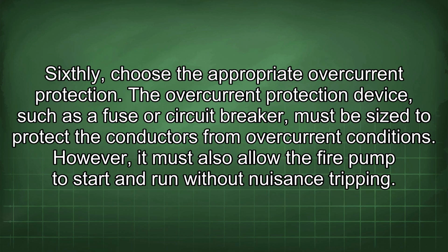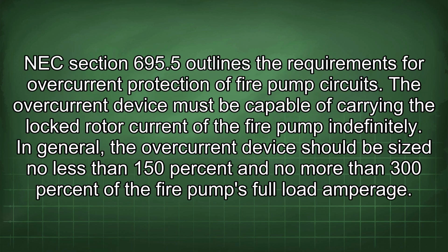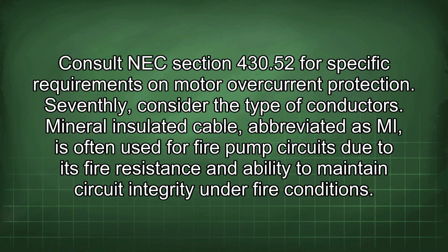Sixthly, choose the appropriate overcurrent protection. The overcurrent protection device, such as a fuse or circuit breaker, must be sized to protect the conductors from overcurrent conditions. However, it must also allow the fire pump to start and run without nuisance tripping. NEC Section 695.5 outlines the requirements for overcurrent protection of fire pump circuits. The overcurrent device must be capable of carrying the locked rotor current of the fire pump indefinitely. In general, the overcurrent device should be sized no less than 150% and no more than 300% of the fire pump's full load amperage. Consult NEC Section 430.52 for specific requirements on motor overcurrent protection.